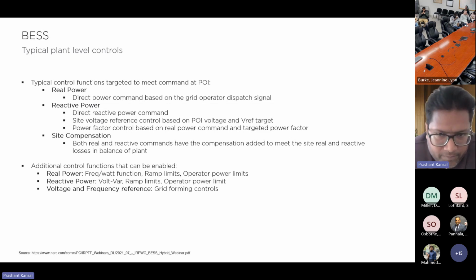And then you have to make sure all those aggregated electrical components are compensated for in the command. So you have to have some kind of compensation in the controls to make sure you meet the command at the POI. On top of that, there are other things you might want, which is what makes it also different from synchronous machine — it's software, so you can do whatever you want with the command, so to say. You can have different frequency-watt, ramps, operator limits, same for reactive power.